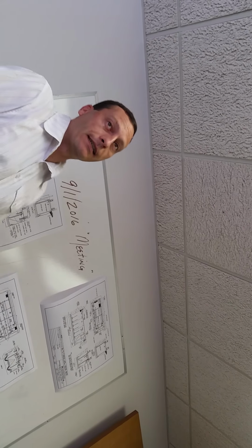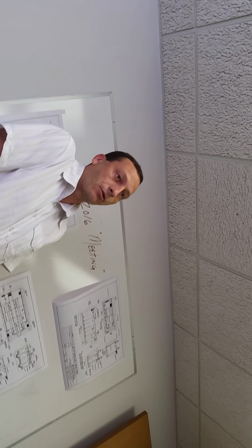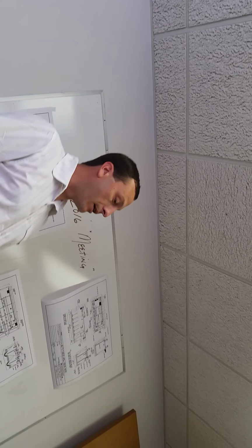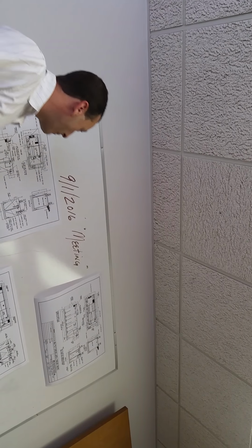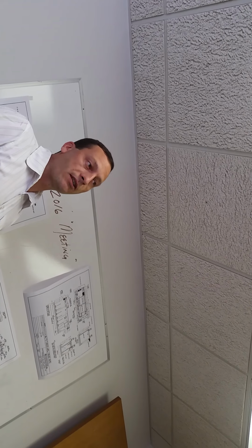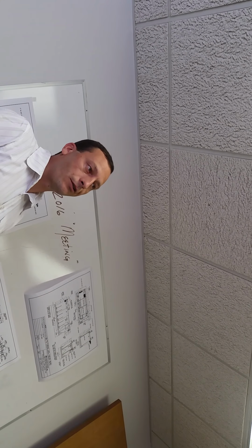From there, we'll try to determine what the waste strength is. Is it an institutional? Is it an industrial? Is it just a domestic application? So we know what waste strength we're going to expect. Extended aeration is pretty much set up for domestic strength waste. We're not going to go at an industrial waste with an EA plant typically. They're sized for 240 BOD and suspended solids coming in.